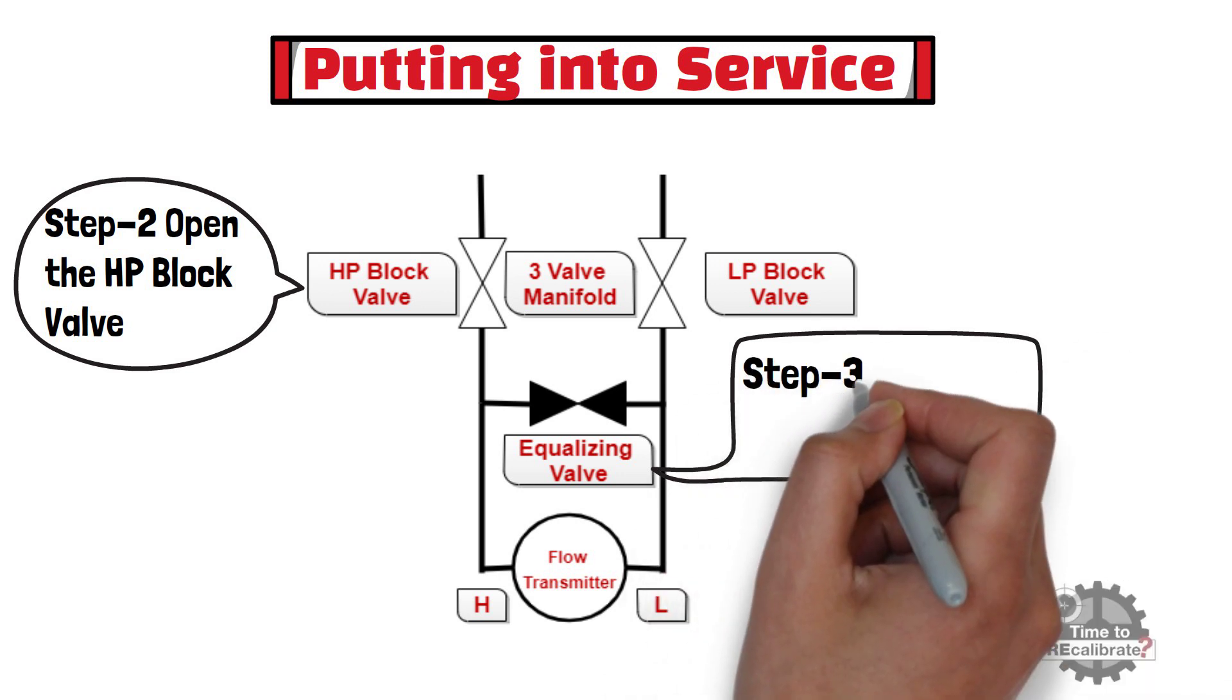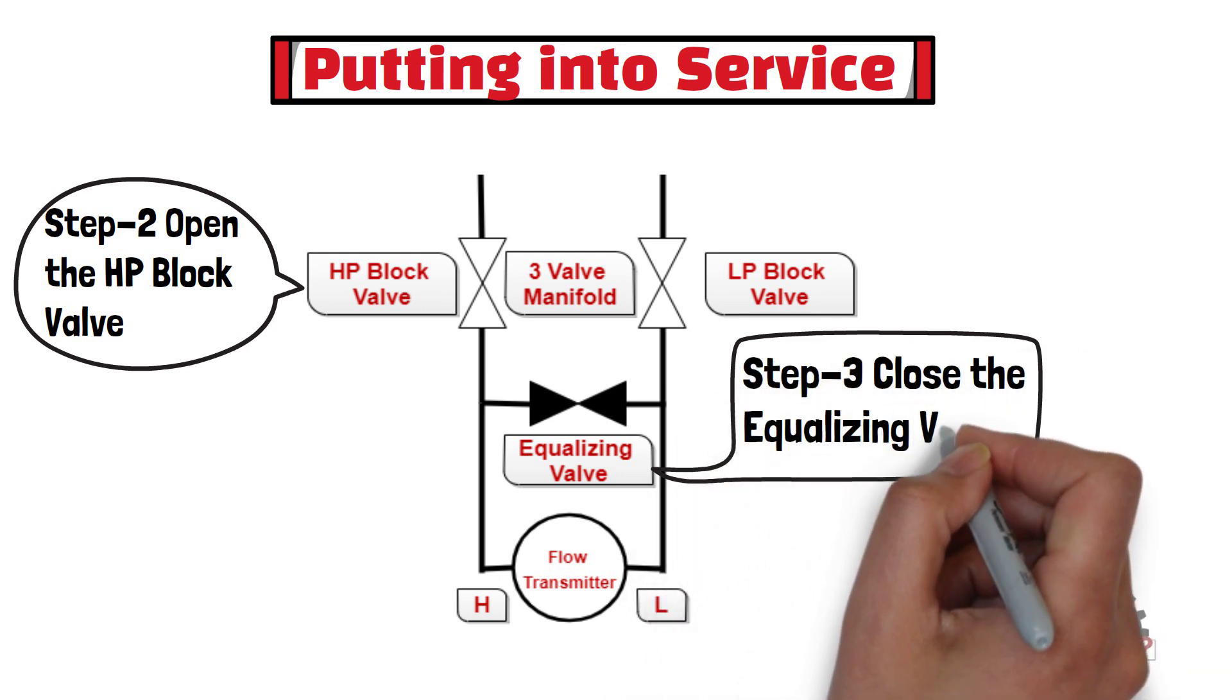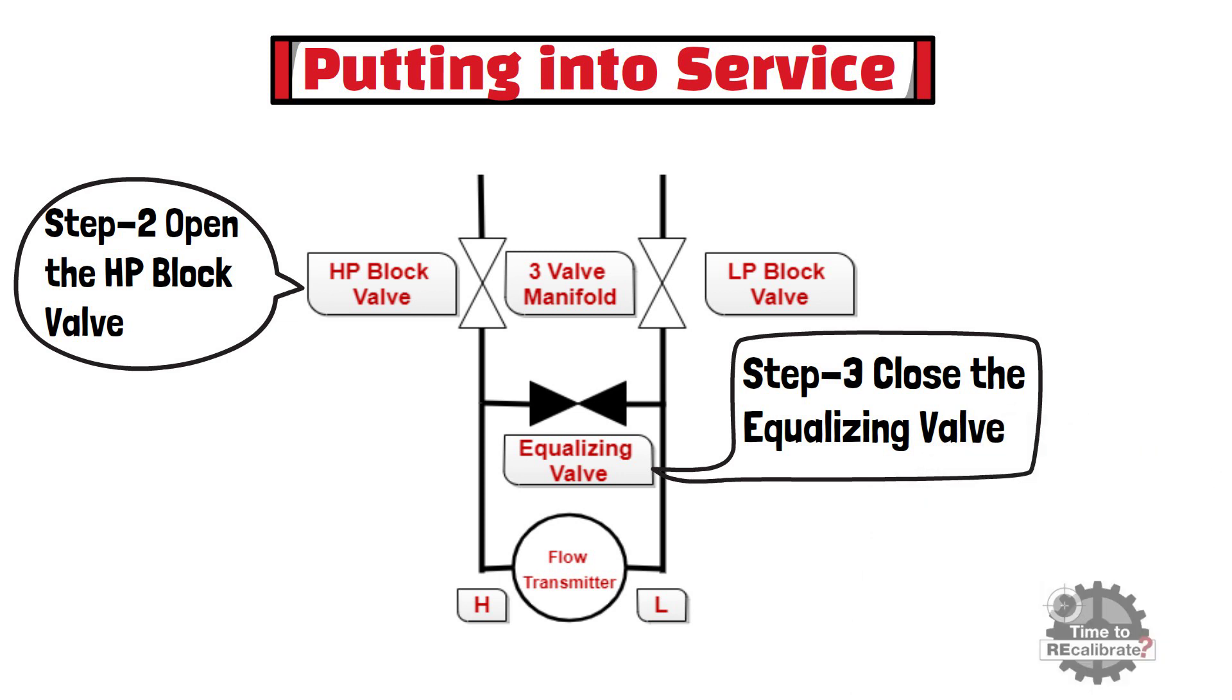Now, in third step, close the equalizing valve by rotating valve in clockwise direction. This will now isolate the HP and LP sides of the transmitter.